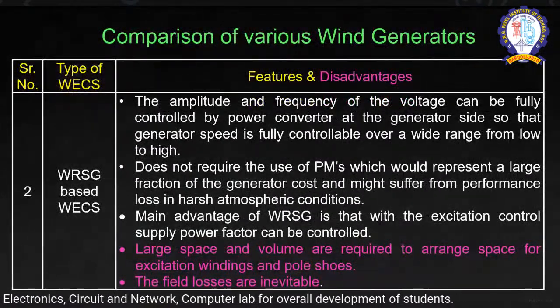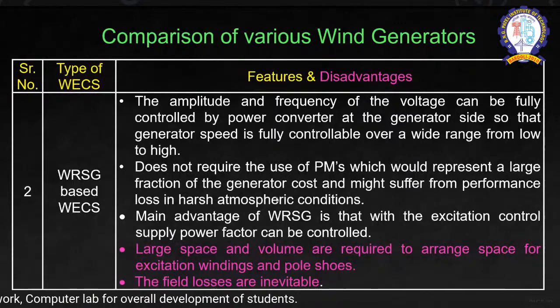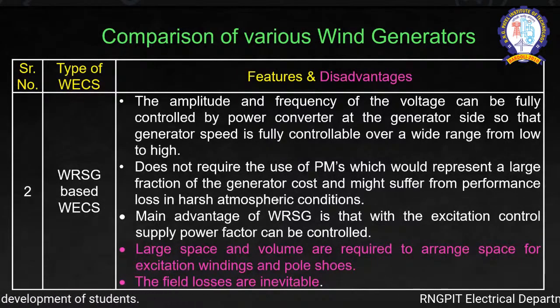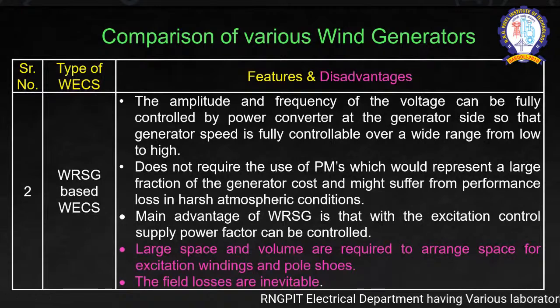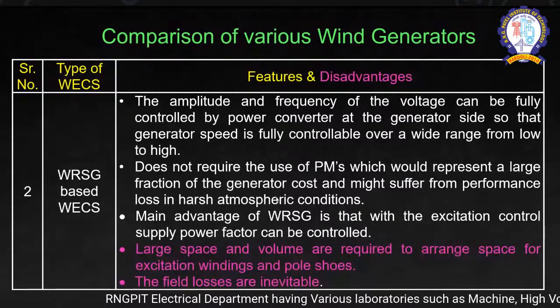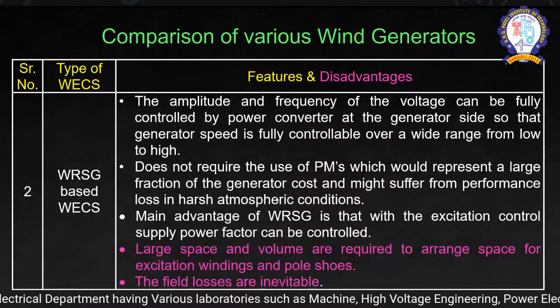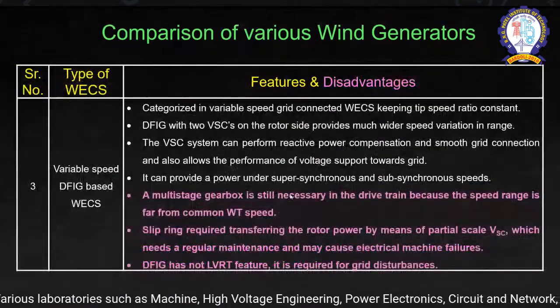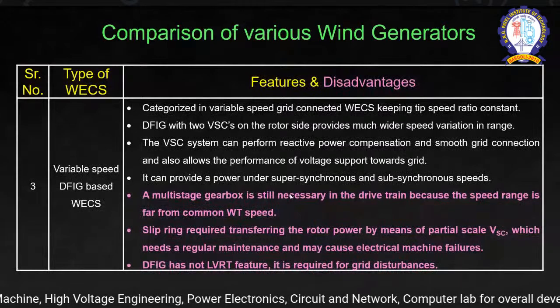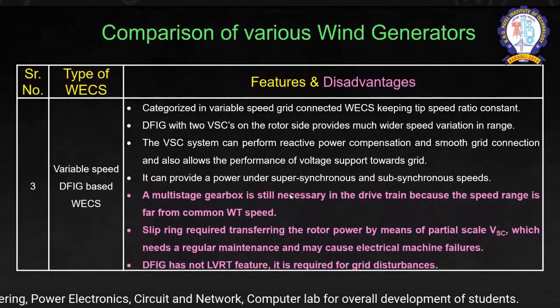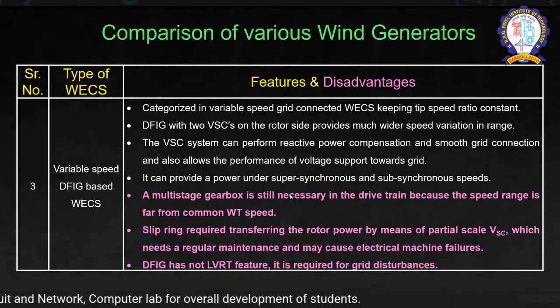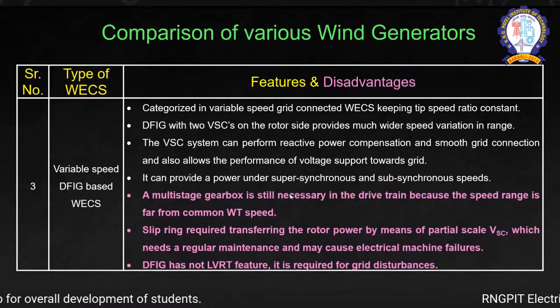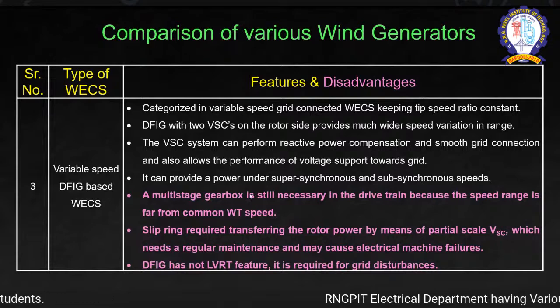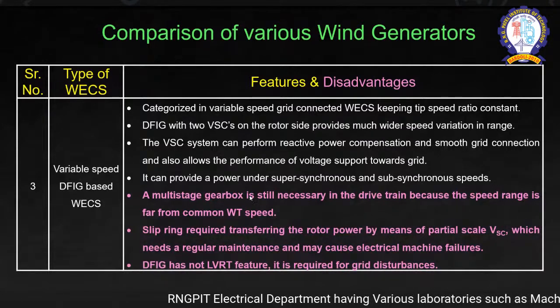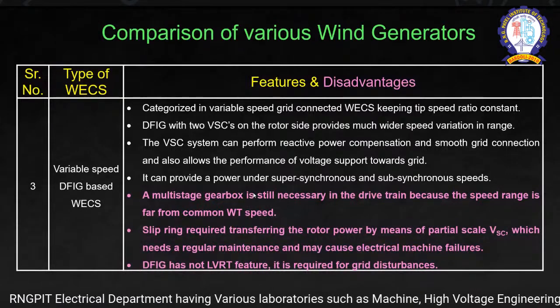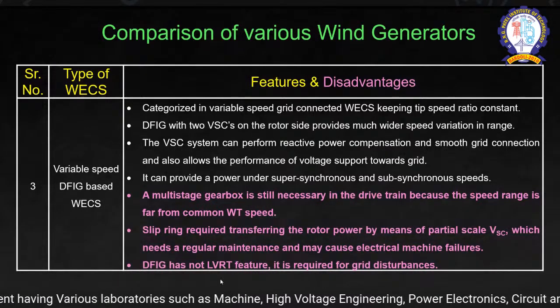Talking about the wound rotor synchronous generator, it requires a very large space to accommodate the excitation winding and pole shoes. Obviously, if you can accommodate this pole shoe, the field losses are obviously more. Talking about a variable speed doubly fed induction machine, we have the slip ring that is required, with rotor power supplied by means of partial scale converters. That is what we call VSC, voltage source converter, which needs regular maintenance and may cause some electrical machine failures. This DFIG was not LVRT capable.